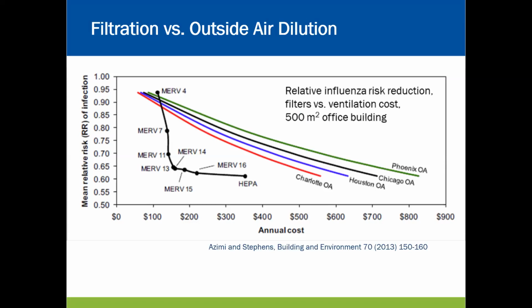When you start getting into a MERV 13 or MERV 14 filter, you've really dropped the relative risk substantially. You can continue to improve the filtration quality all the way up to HEPA filtration, but it adds quite a bit more cost, and it decreases the relative risk of infection, but not substantially.